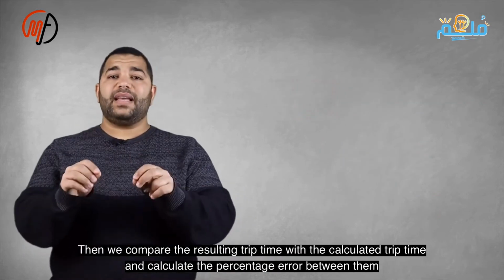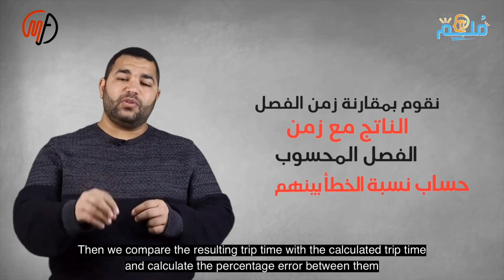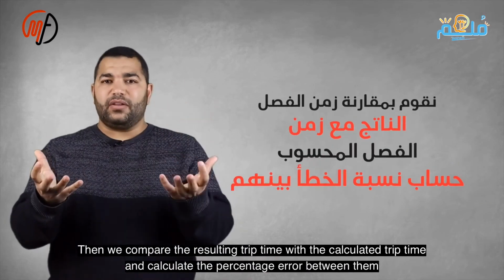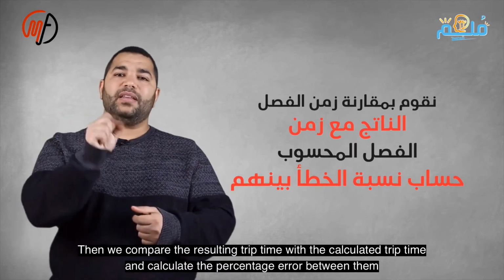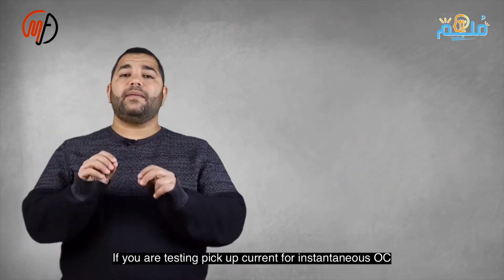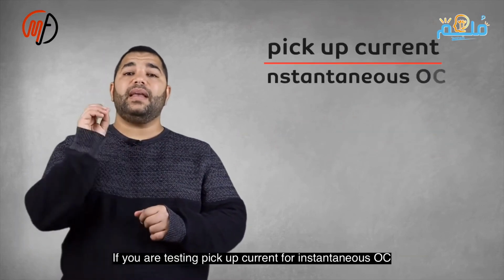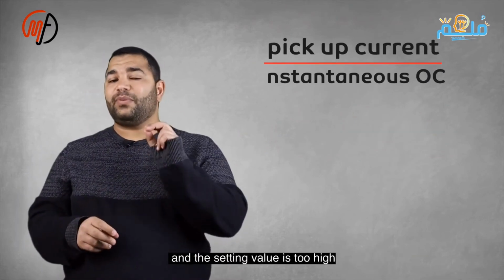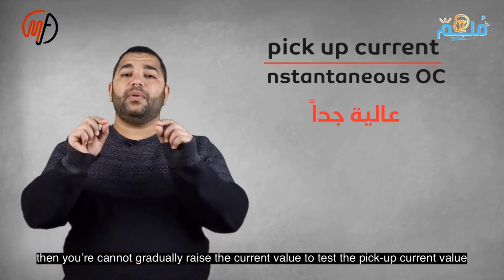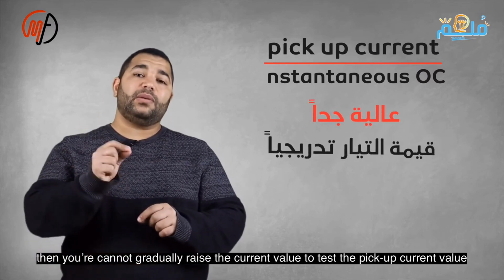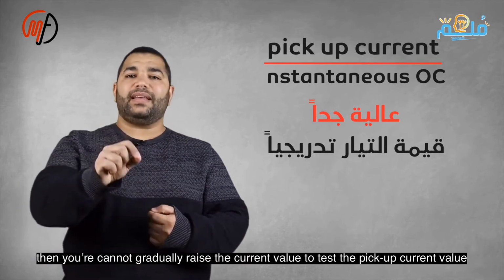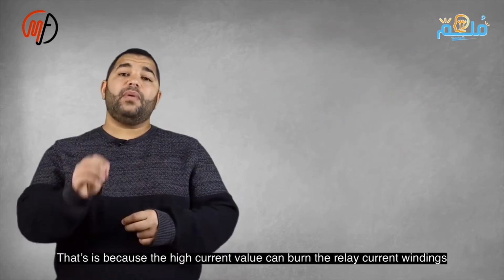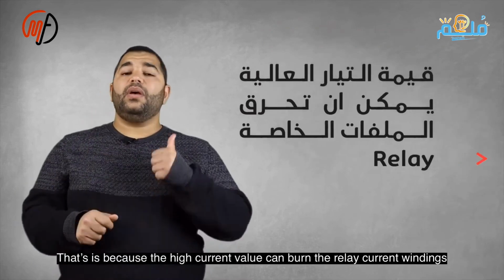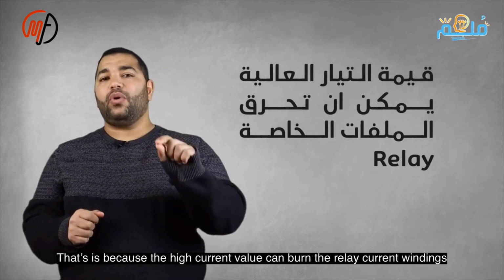For testing pickup current in instantaneous overcurrent, if the setting is high, gradually increasing the current is not feasible as it may damage the relay. We test in pulses, increasing the current stepwise and performing on-off tests until the relay operates. Continuous injection is avoided, and drop-off current testing is unnecessary. For earth fault, the method is similar to overcurrent, but tested only on the neutral.